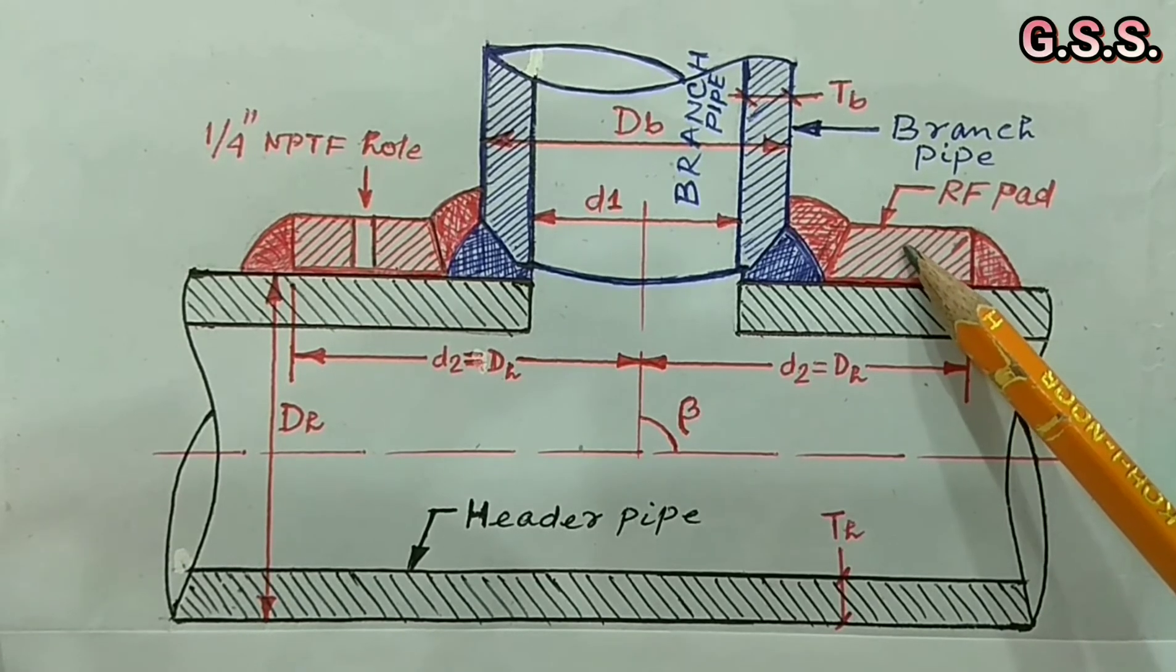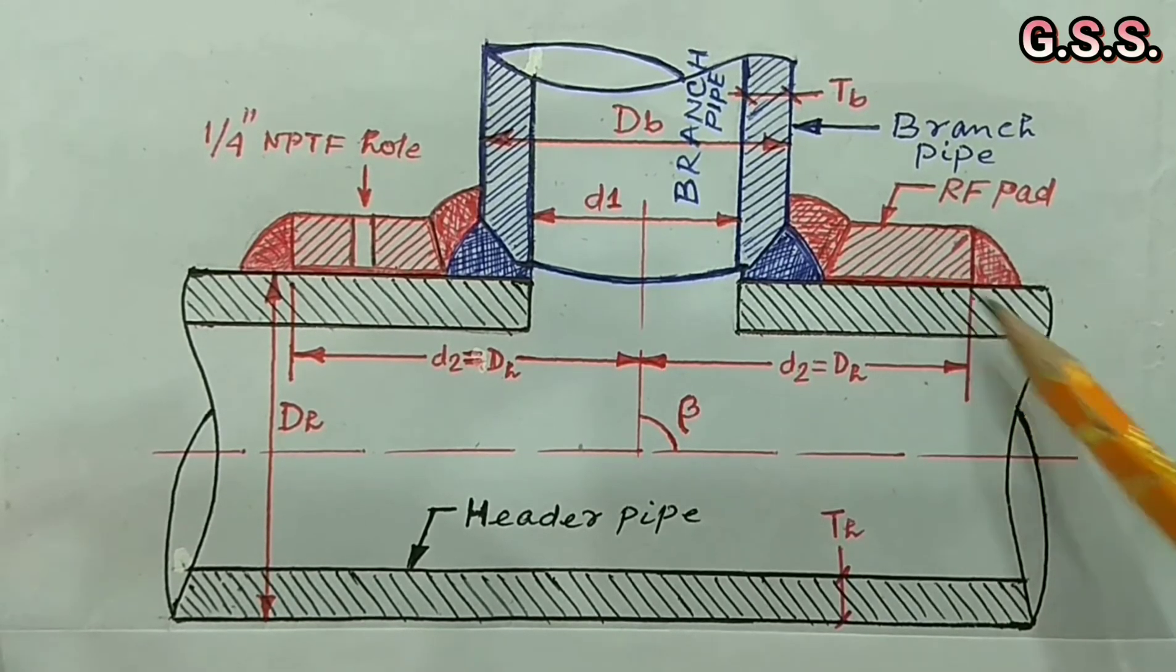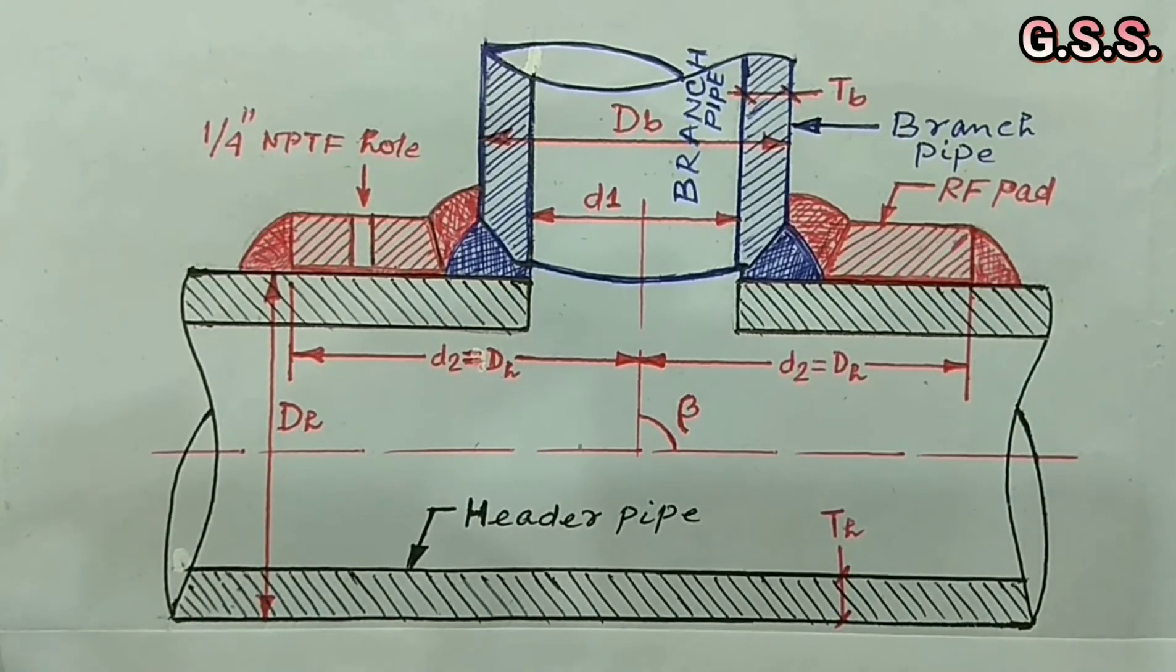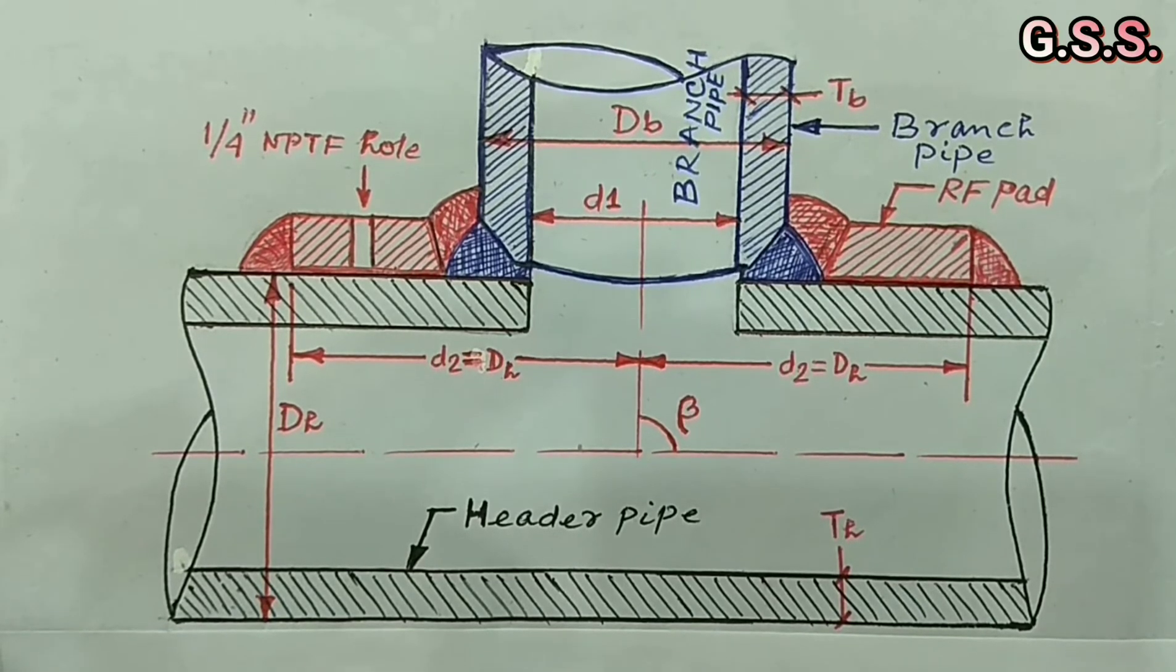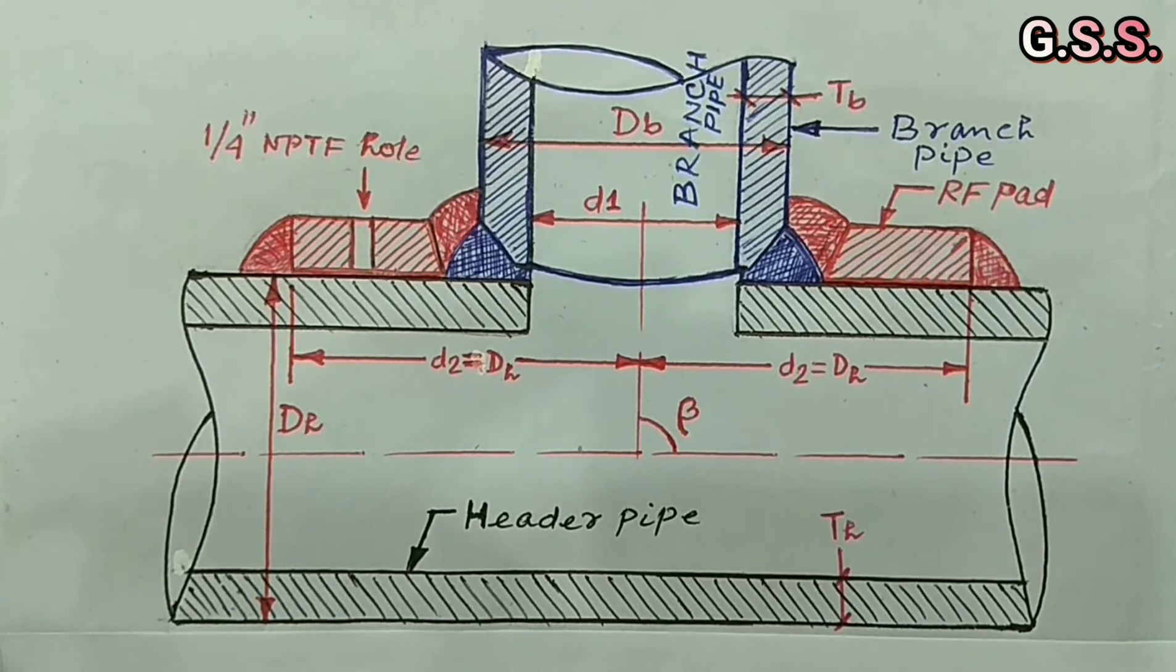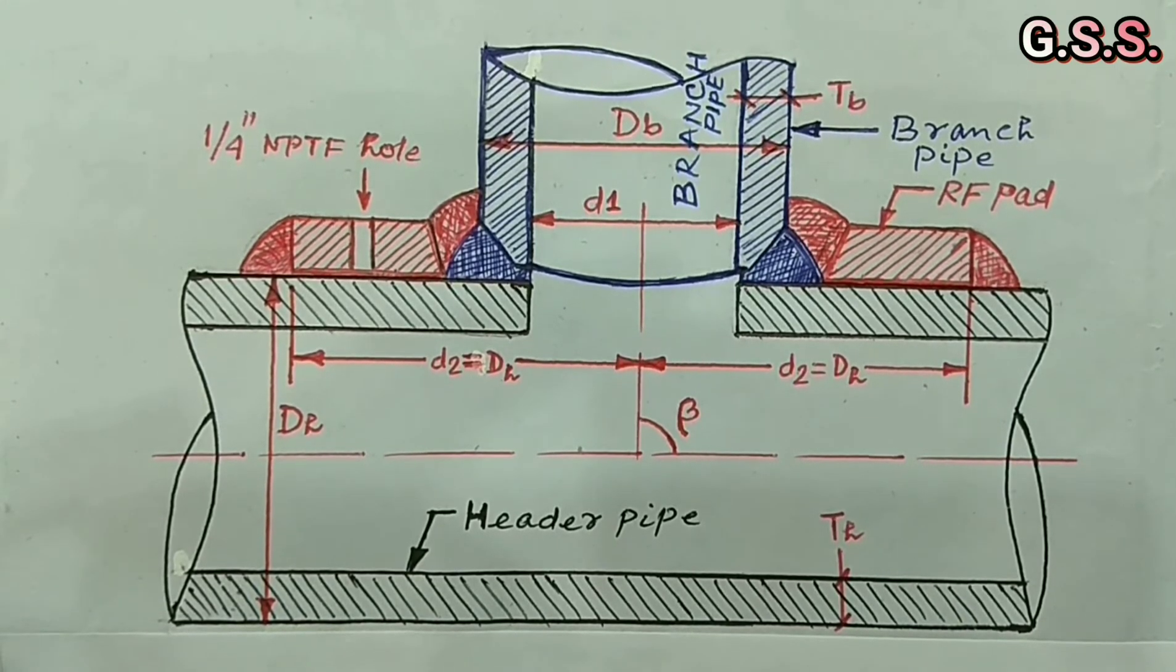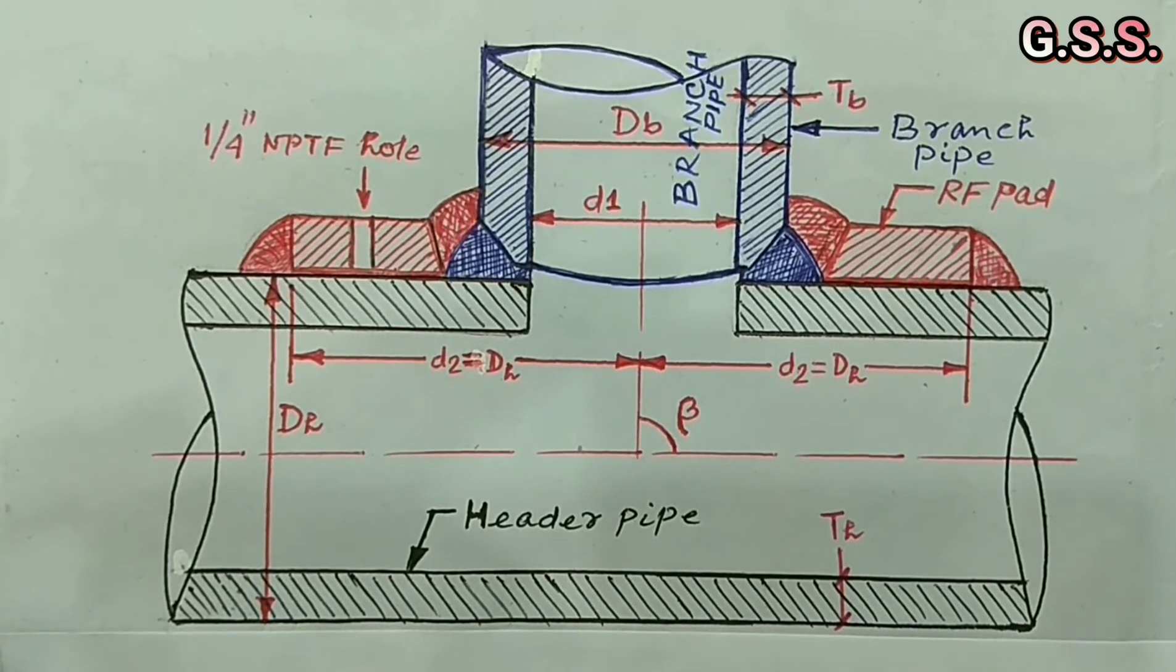That means reinforced branching. It may happen that reinforced branching is found safe from internal pressure calculation but it fails in pipe stress analysis. Then we have to go for butt weld tee.